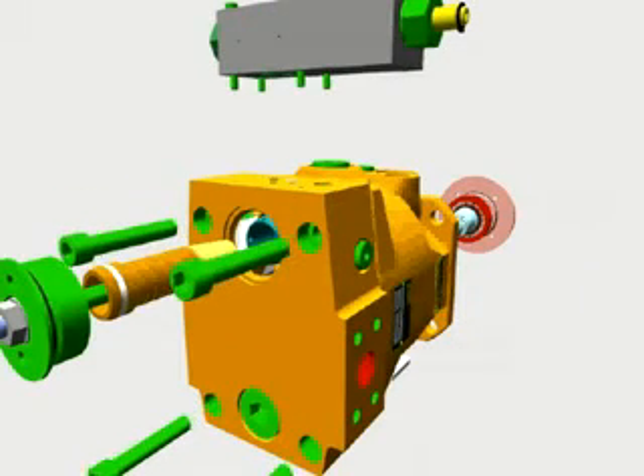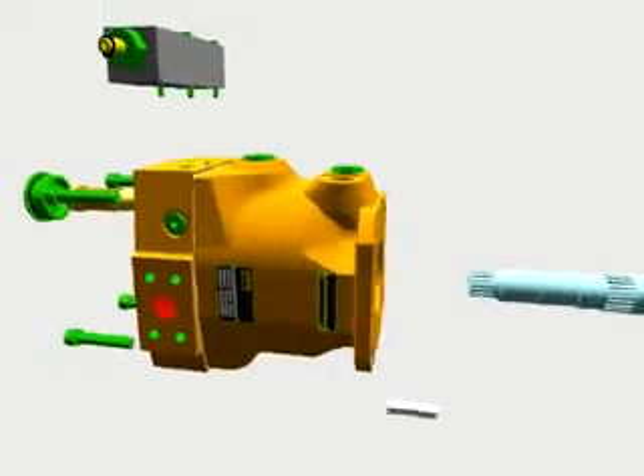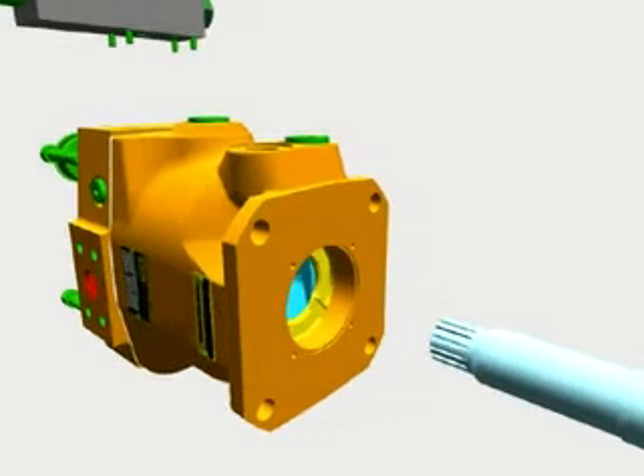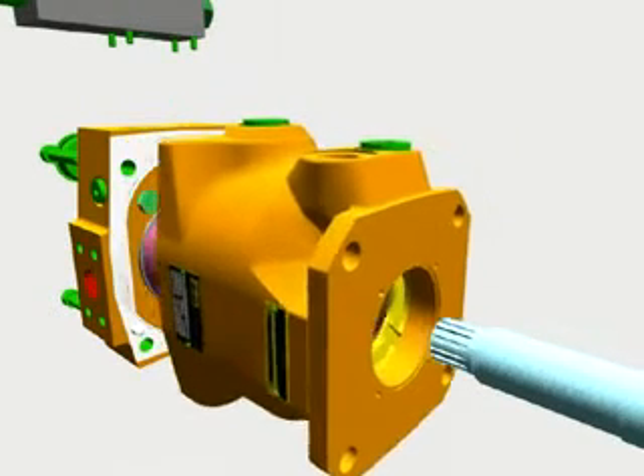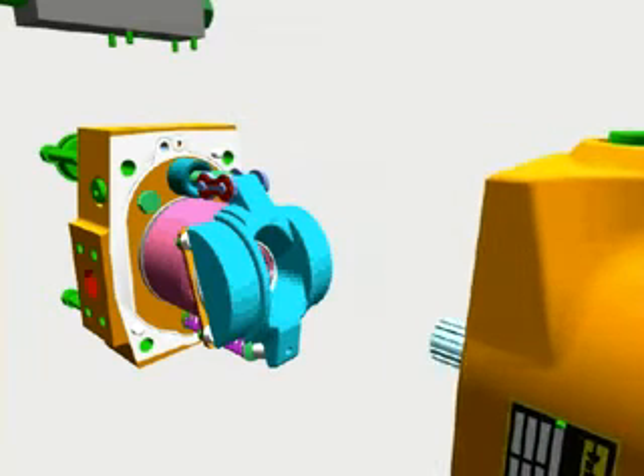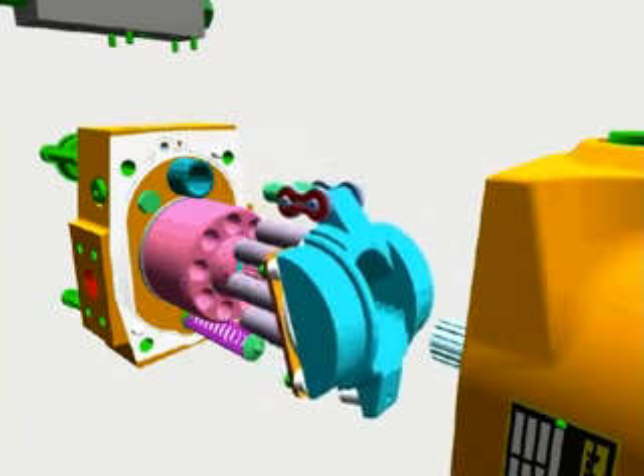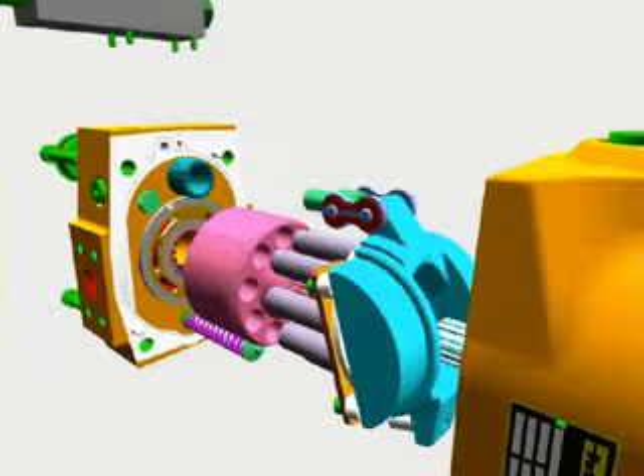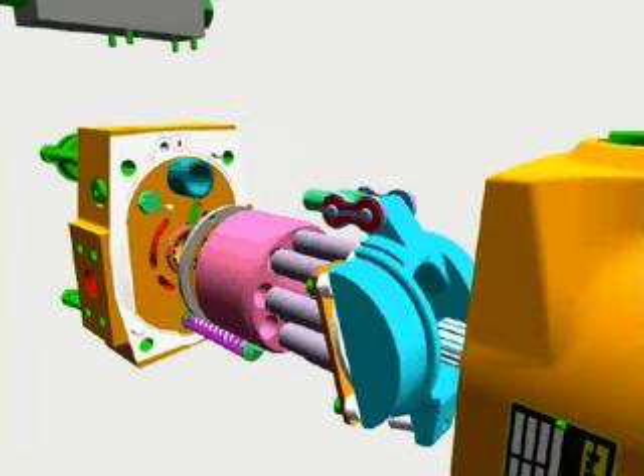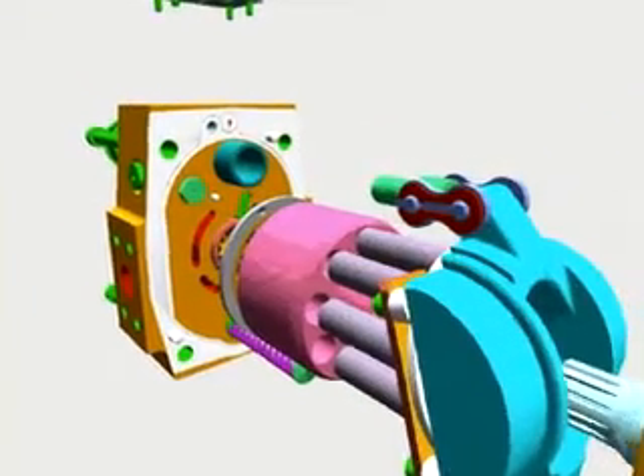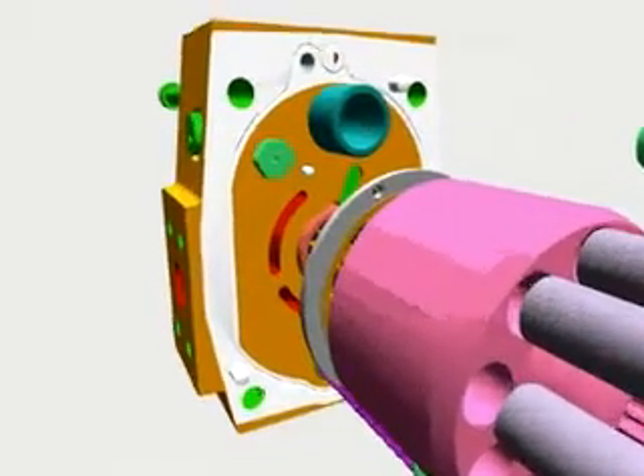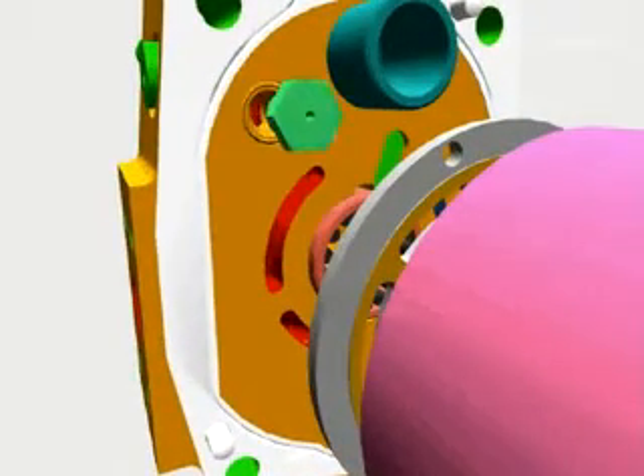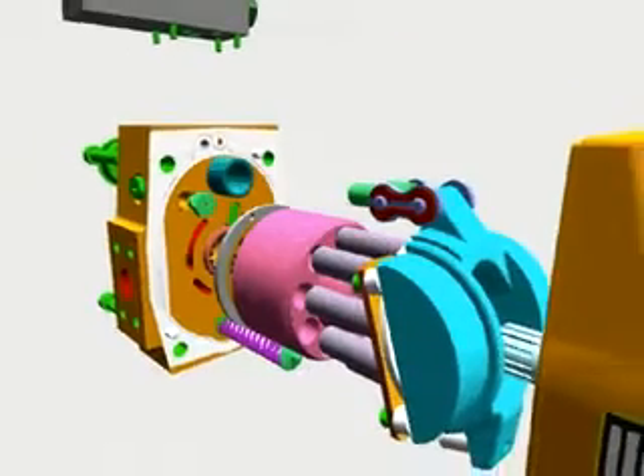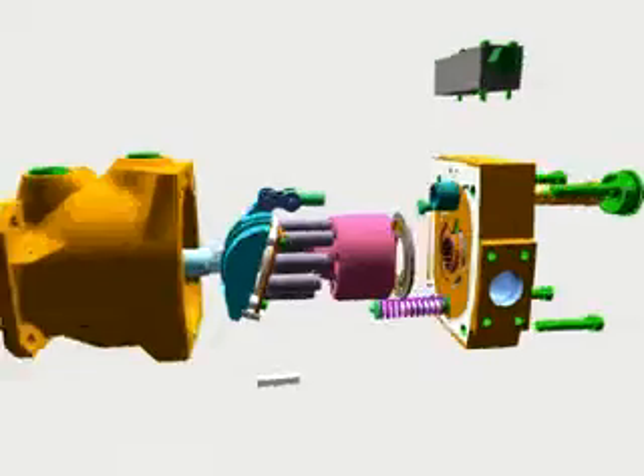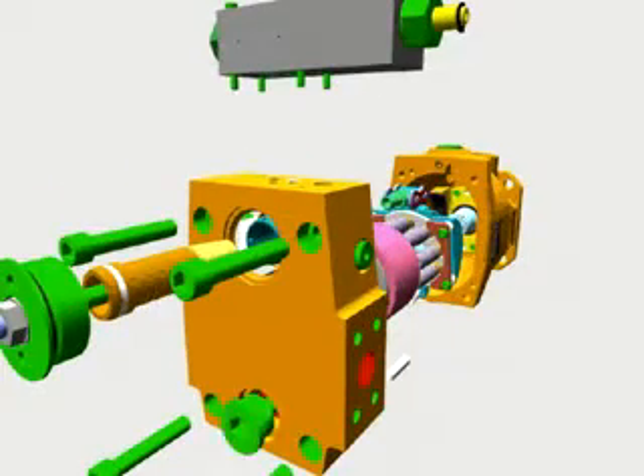After removing the 4 body screws, which are available in both metric or UNC sizes, we get to the heart of the pump. Removal of the pump case provides access to the rotating group, including the swash plate, the cylinder block, the pistons and slippers, and the valve plate. In addition, we find the integrated air bleed valve, which shortens the startup of a new system and ensures quick priming, quieter system operation, and improved system reliability. Finally, we take out the spring cover with the bias spring.